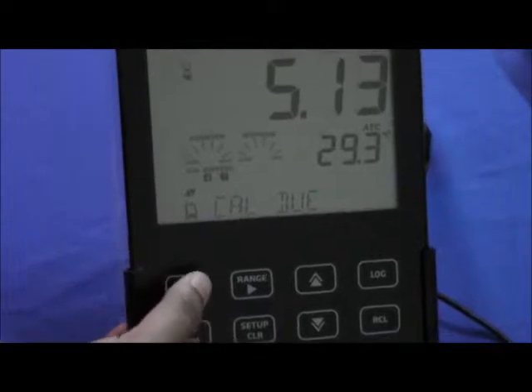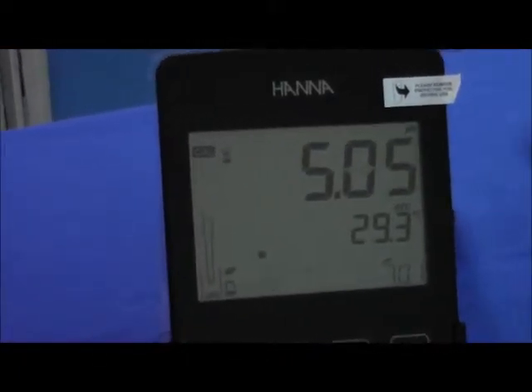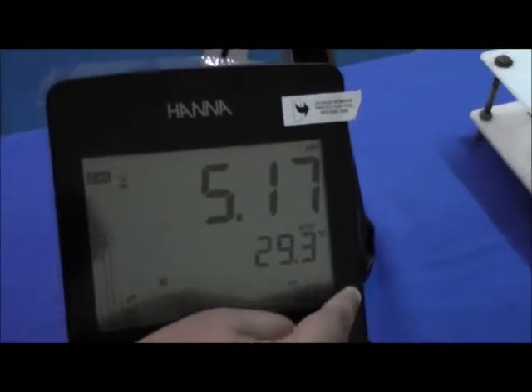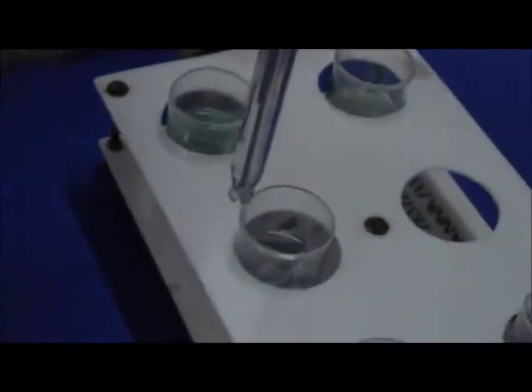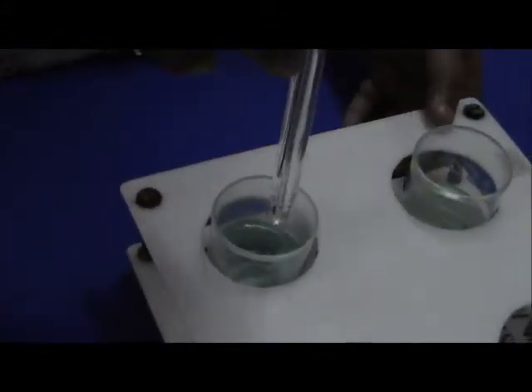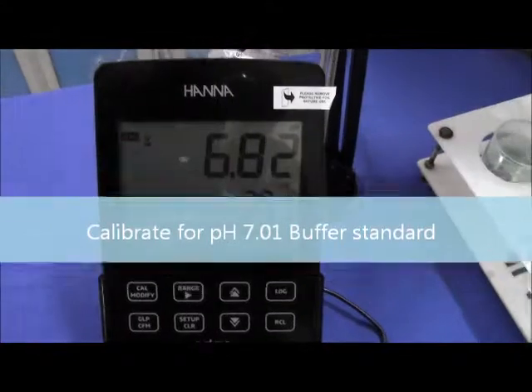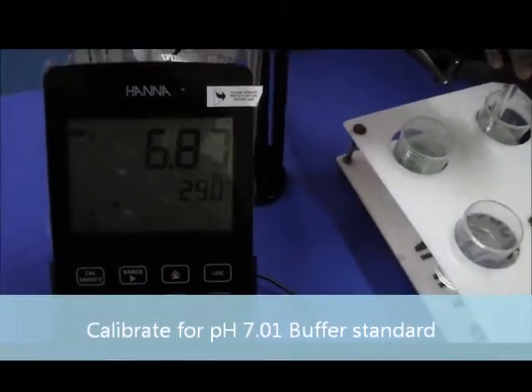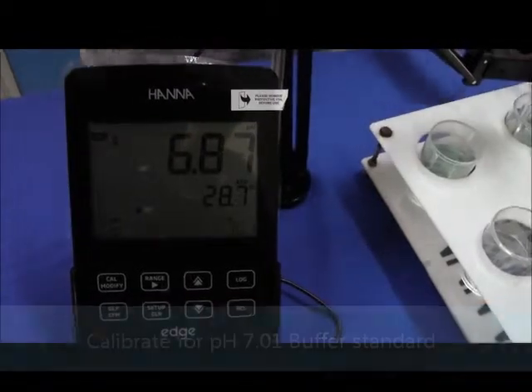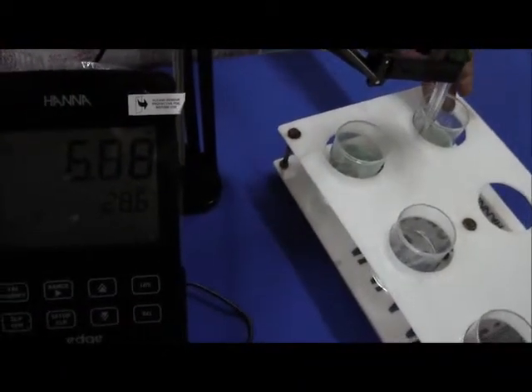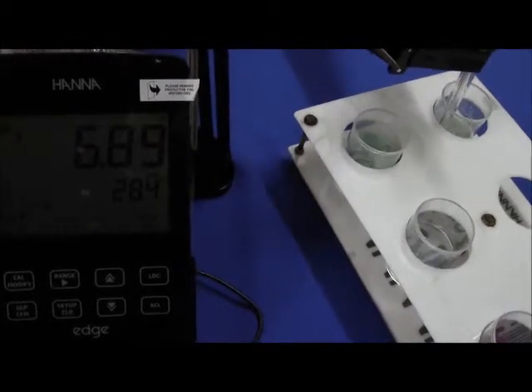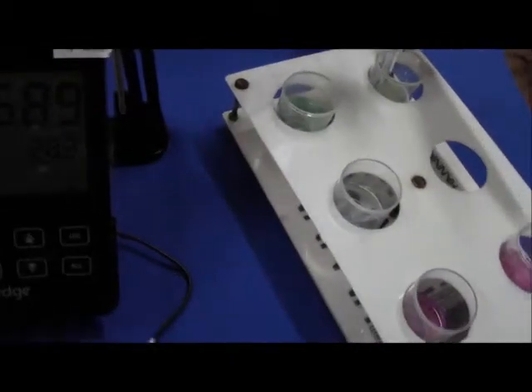We would now calibrate the meter for pH. We would switch on to the calibration button. It is now asking for pH 7.01. We'll dip the electrode into the pH 7.01 buffer solution. It is recommended to activate the pH electrode in pH 4 solution for 5 to 10 minutes before calibrating the meter.